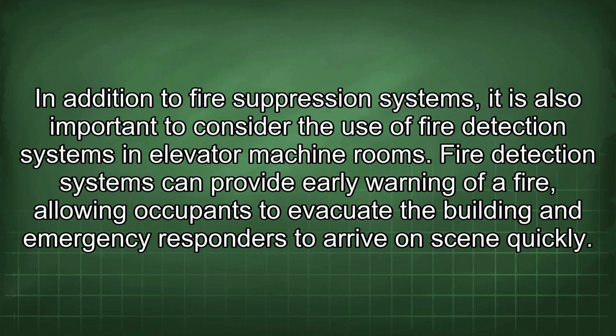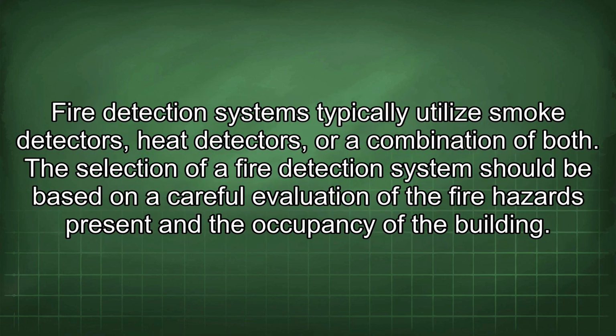In addition to fire suppression systems, it is also important to consider the use of fire detection systems in elevator machine rooms. Fire detection systems can provide early warning of a fire, allowing occupants to evacuate the building and emergency responders to arrive on scene quickly. Fire detection systems typically utilize smoke detectors, heat detectors, or a combination of both. The selection of a fire detection system should be based on a careful evaluation of the fire hazards present and the occupancy of the building.